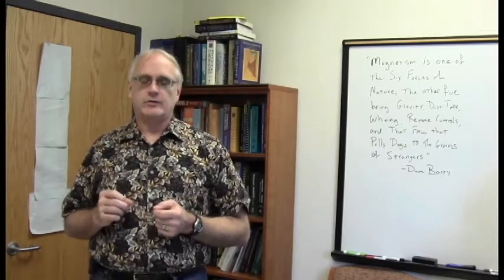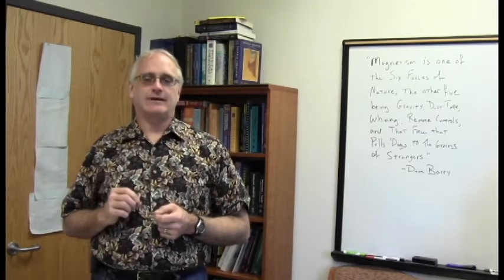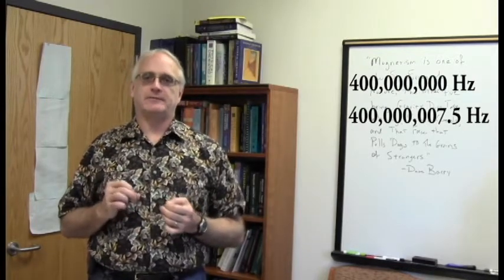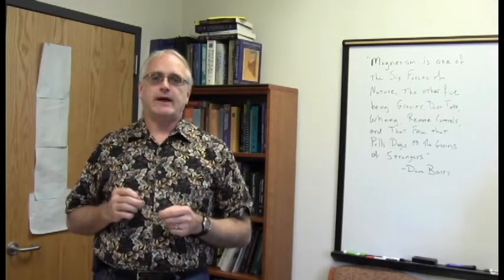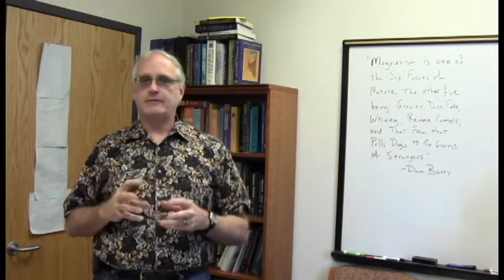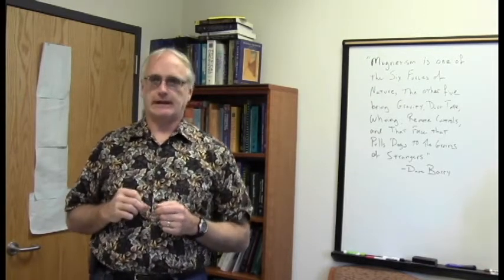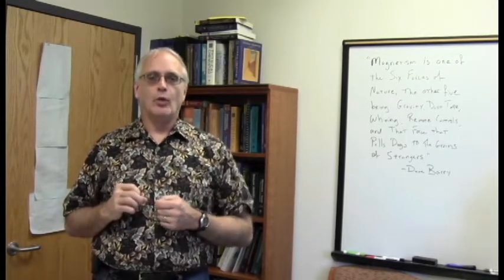It's like being able, for the instrument, to pick up the difference between one peak at exactly 400 megahertz — 400 million hertz — and the next one at 400 million and 7.5 hertz. That's a difference in the ninth decimal place. That is extraordinarily difficult to achieve. What that means is the magnetic field felt by every proton in our sample, in order to achieve resolution like this, cannot vary by more than about one in a billion.